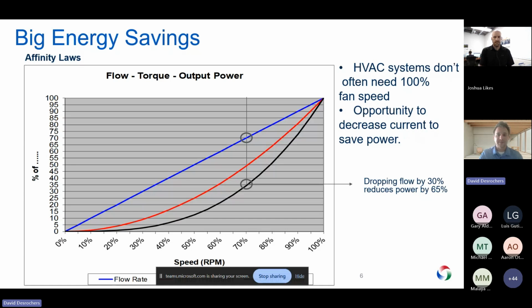So rarely do HVAC systems always need 100% fan or pump speed. And so what that allows us to do with a VFD, instead of pushing against a damper or a valve, we can get rid of the damper or the valve and instead just use the VFD to control our flow. So as you can see, if you drop flow rate in either water or air, CFM, GPM by around 30%, you're going to get a reduction in power of around 65% in electrical power.